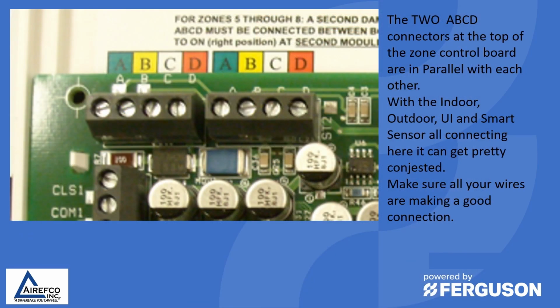When using a zone control board, the 2 ABCD connectors at the top of the zone control board are in parallel with each other. With the indoor, outdoor, user interface and a smart sensor all connecting here, it can get pretty congested. Make sure that all your wires are making good connections on these points.